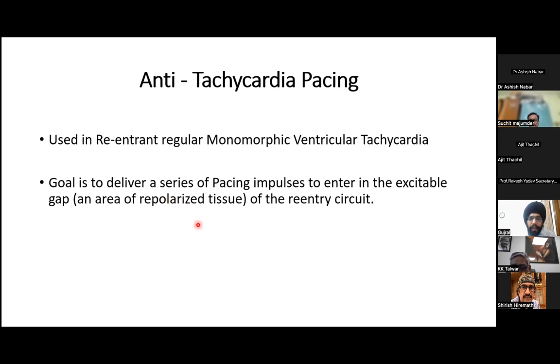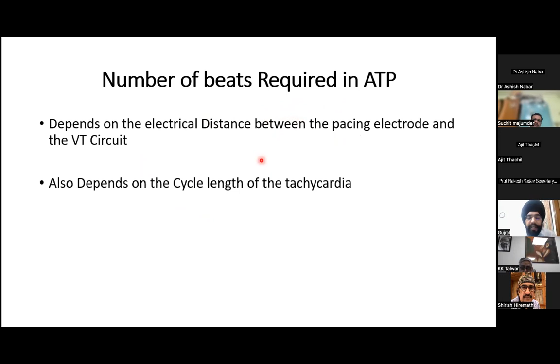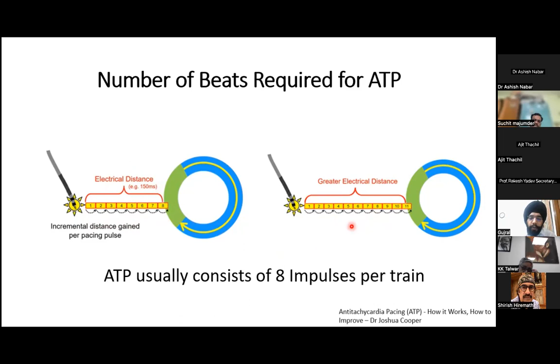So then the question comes in anti-tachycardia pacing, how many beats should you give? Should you give just 1 beat, 2 beats, 3 beats, 4 beats? That depends upon the distance between the pacing electrode and the VT circuit. For the panel on the left, suppose the distance is this much. What is important is the electrical distance, not the anatomical distance. If the electrical distance is this much, in this particular case 8 impulses are required. In the panel on the right, the electrical distance is more, so you may require more impulses. But what studies have shown consistently is that ATP works efficiently if you have 8 to 10 impulses per train.